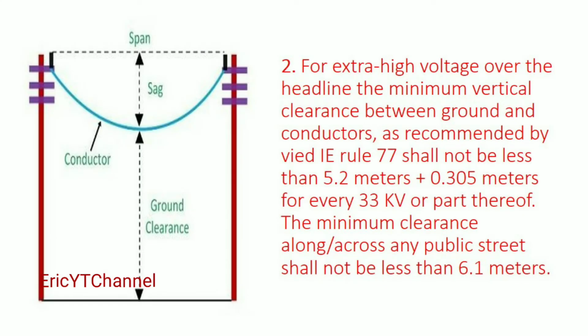Number 2. For extra high voltage over the headline, the minimum vertical clearance between the ground and conductors, as recommended by IE Rule 77, shall not be less than 5.2 meters, plus 0.305 meters for every 33 kilovolt or part thereof. Minimum clearance along or across any public street shall not be less than 6.1 meters.